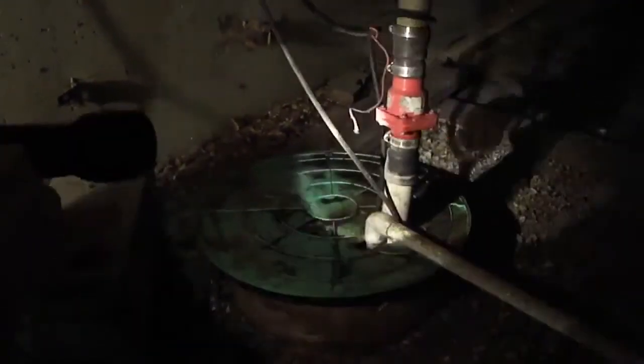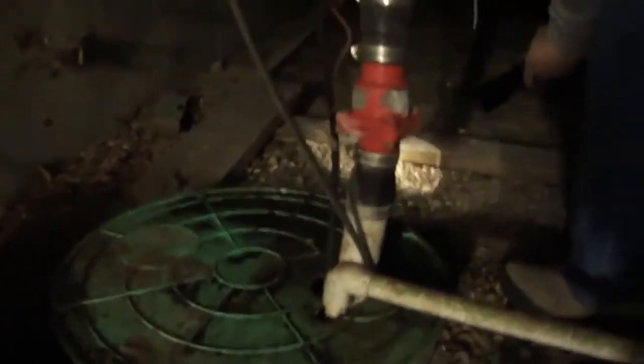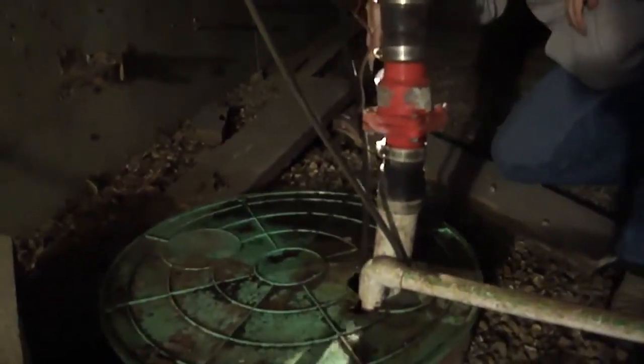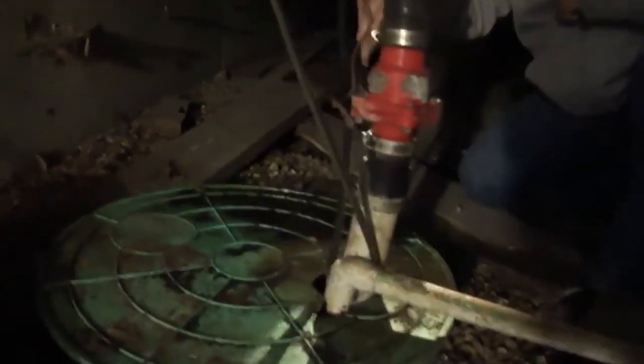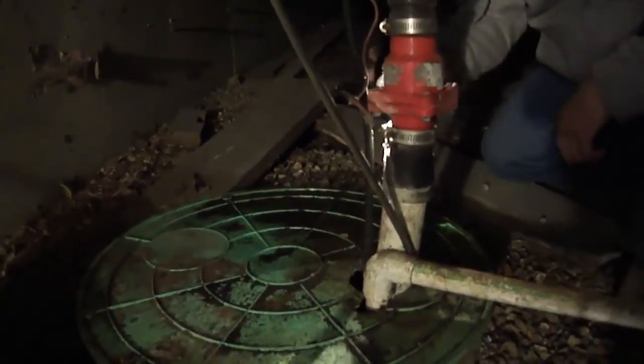Your check valve is leaking. What? The check valve. Oh, that's not good. So what does that mean? It should be replaced eventually. Can you tell from water corrosion? No, because I'm seeing it leak — right here, this leak right here.